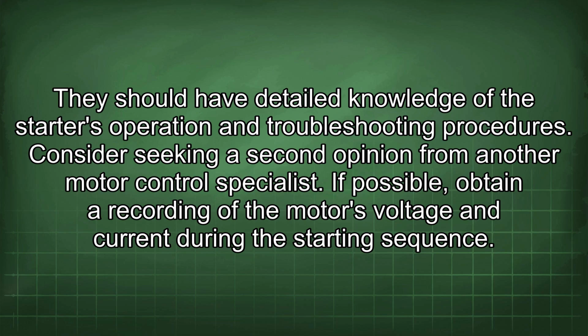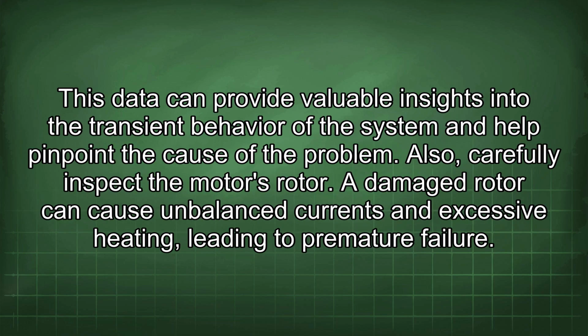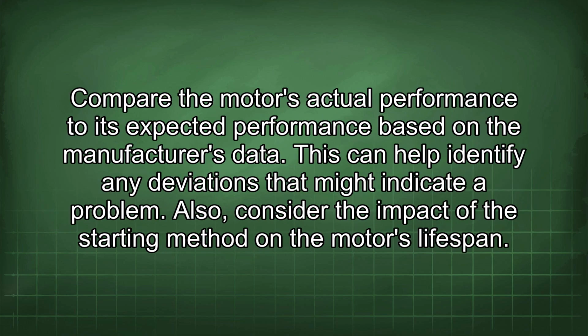If possible, obtain a recording of the motor's voltage and current during the starting sequence. This data can provide valuable insights into the transient behavior of the system and help pinpoint the cause of the problem. Also, carefully inspect the motor's rotor. A damaged rotor can cause unbalanced currents and excessive heating, leading to premature failure. Compare the motor's actual performance to its expected performance based on the manufacturer's data. This can help identify any deviations that might indicate a problem.